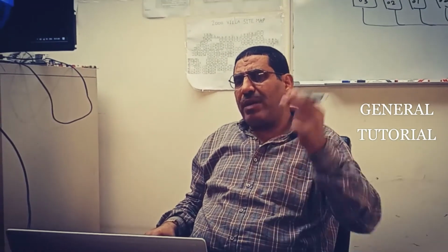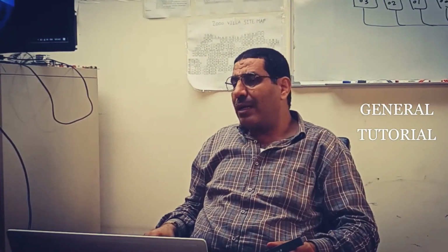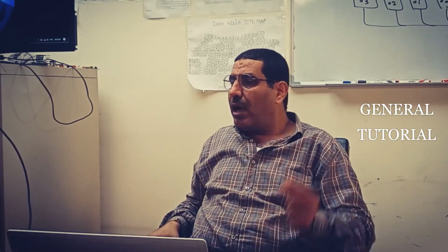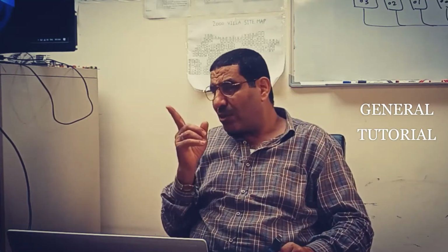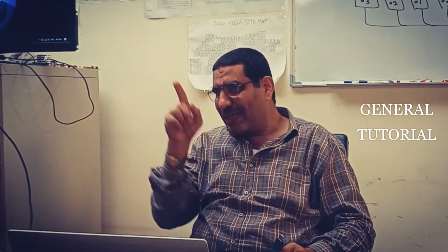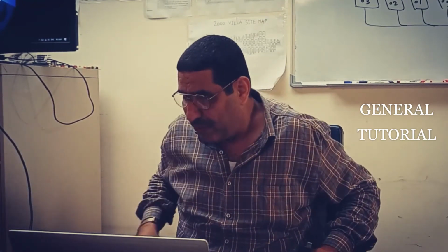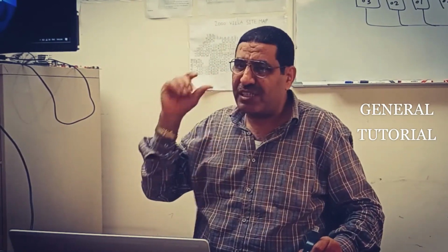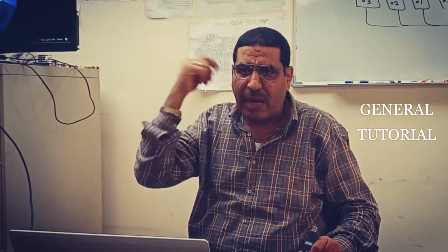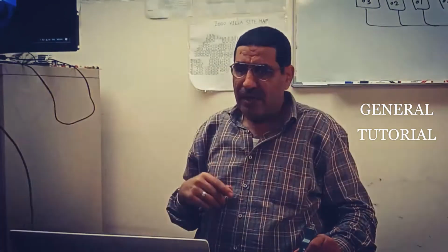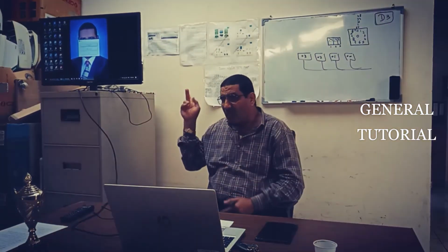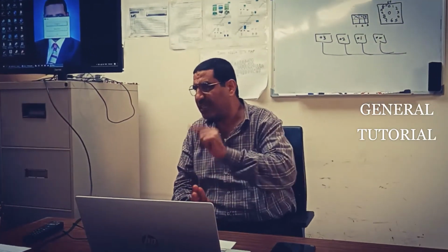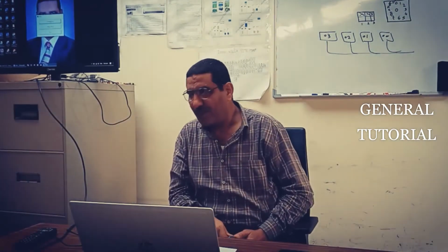Okay, which terminal in indoor? X1, X2. Which terminal in outdoor? X1, X2, or Z1, Z2. You remember before I said Z1, Z2. When we reach that, we will talk about it. Okay? Yeah, I can connect the service tool at Z1, Z2 in the outdoor unit or at X1, X2. It's the same. Okay?